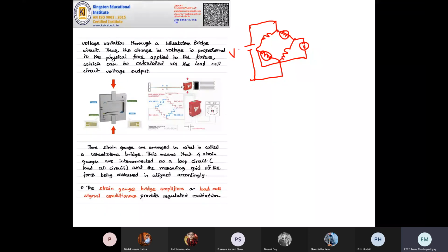That voltage is called excitation voltage. For any given configuration of this strain gauge Wheatstone bridge, if you increase the excitation voltage, your output voltage will increase. So there is another reading, or normalized reading, called mV per V. Before we come to that, the proper excitation voltage, or we can say the optimal value of excitation voltage, is given by your strain gauge bridge amplifier.